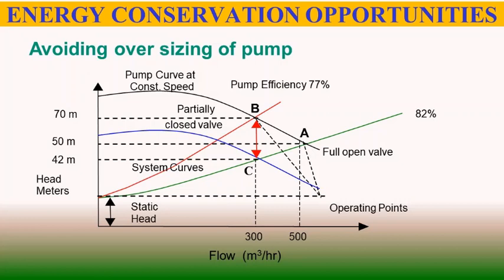I mean, they are not changing the system resistance, but they are changing the pump performance curve and thereby reducing the total capacity control of the flow.